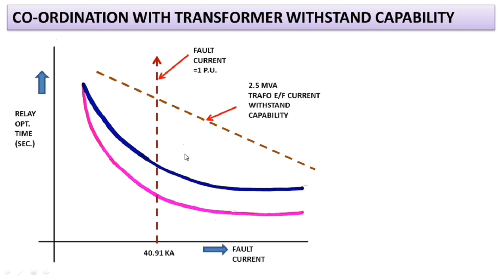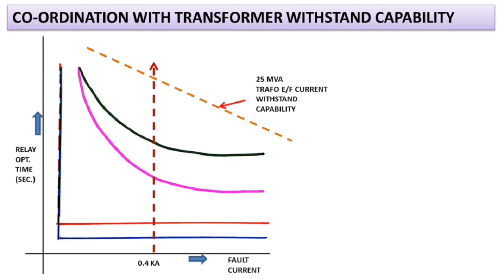The relay curves must be coordinated with the transformer earth fault withstand capability curve. The 2.5 MVA transformer earth fault withstand capability curve must lie above both relay characteristics, and the 25 MVA transformer withstand capability similarly. This is the most important part of relay settings — relays must always operate before the fault exceeds the withstand capability of the equipment.